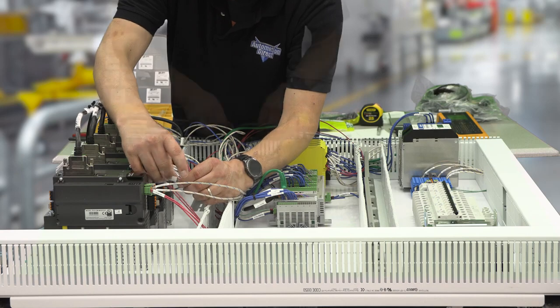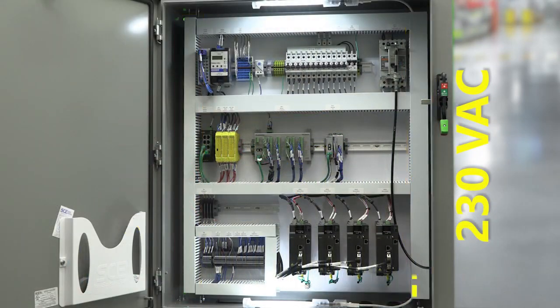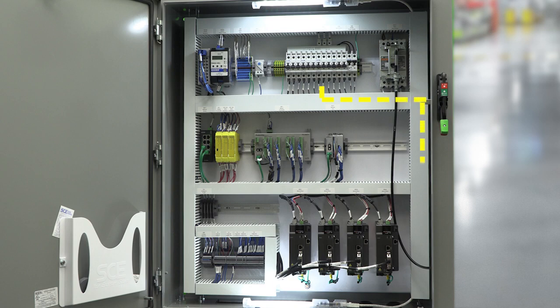Route wires carefully so higher voltages stay away from lower voltages. For example, on this panel, we've routed the 3-phase power up the right side duct through the main disconnect and back around to the AC circuit breaker bus lugs. Then the AC power wires run out of the bottom of the breakers and back down the right side of the panel to the 4 servo drives.